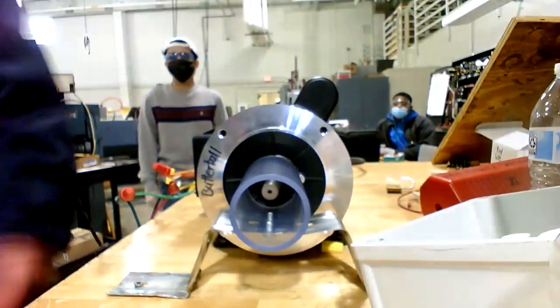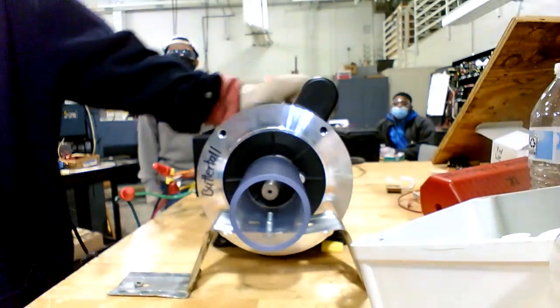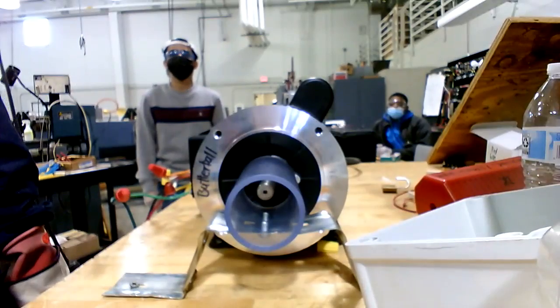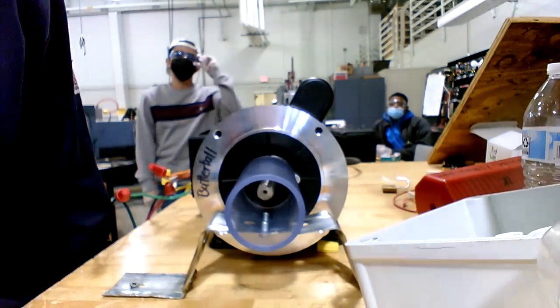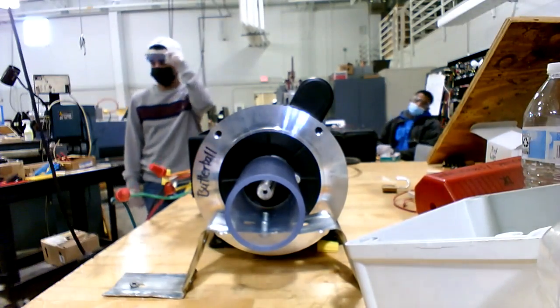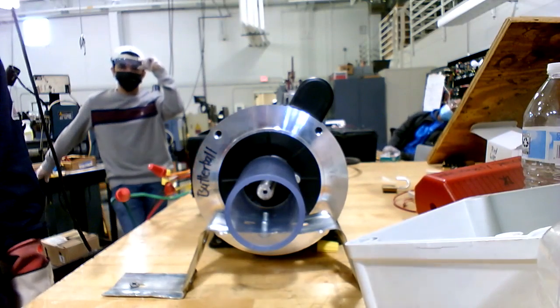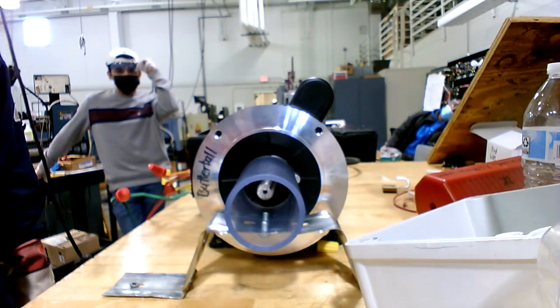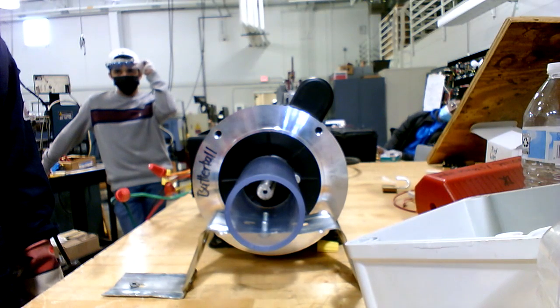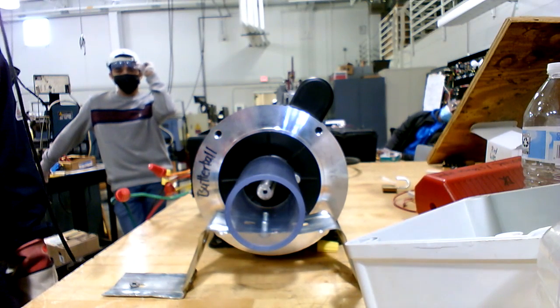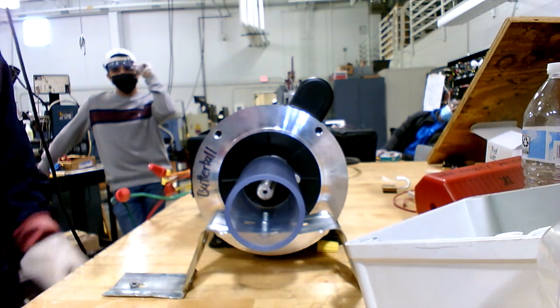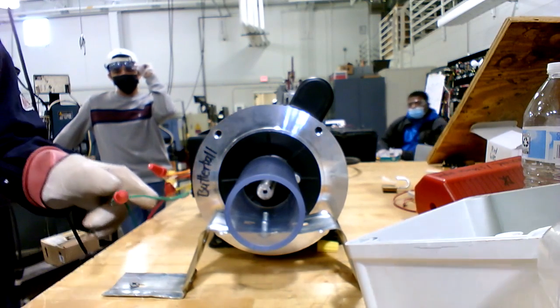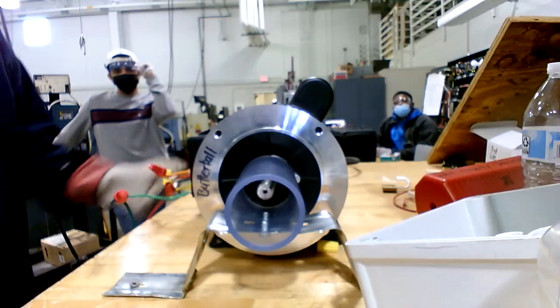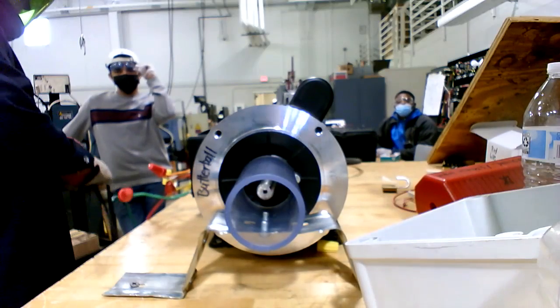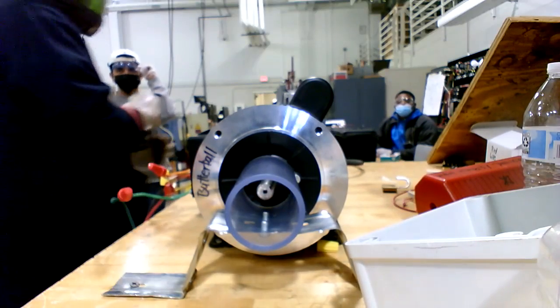So, turn it on. Turn it off. Notice the rotation. See, it's going clockwise. See it? Now, to make it go counterclockwise, you might have a fan that's an intake fan on one, you might have an exhaust fan. So on a farm or wherever you're at, or in industry, you may have to make that motor go the other way. So we're going to let you flip it. So look, you're going to lock it out. Disconnect the main power line and I'll put that lockout back on the plug.